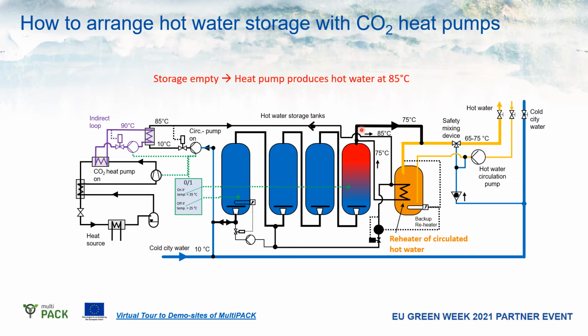So this 85-degree water is entering a first heat exchanger. Inside it can be a plate heat exchanger or a tank or whatever, to reheat the circulated water to the building. If this is a hotel or other places, you always have a hot water circulation loop, and the returning water from the building has to be reheated before going back into the loop. And this preheating can be done with the 85-degree water coming from the heat pump, reheating the water, and maybe 10 Kelvin lower, the 75-degree water is entering the tank and is accumulated here. So the cold water is pushed and taken by the pump through the heat pump.